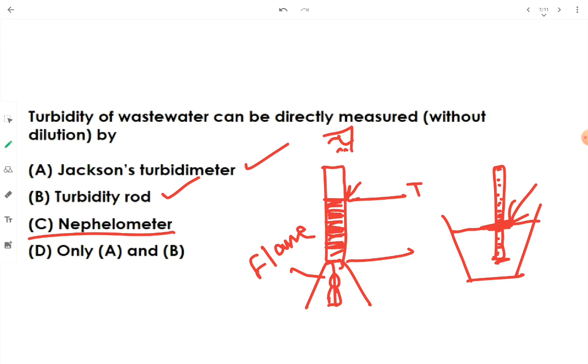The point at which this end of the turbidity rod is not at all visible, the surface touching this specific rod will be recorded as the turbidity of the wastewater. The marking that the surface is in contact with will be recorded as the turbidity. This is how, as simple as that, the Jackson turbidimeter and turbidity rod are used without any dilution process.